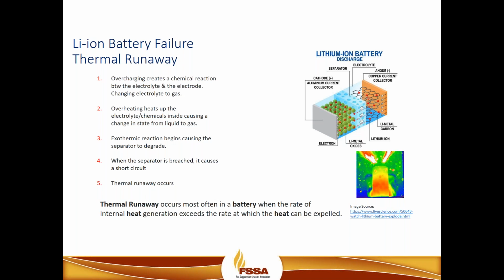If we look at what allows the electrolytes to become a gas, previously we talked about overcharging. So when overcharging is in the chemical process, the anode has too much current and it is touching the liquid. This allows for the chemical reaction to occur and change state from a liquid to a gas, and that's how it changes state. So as I mentioned, during this change of state, it happens at a relatively low temperature, usually at around, let's say, about 115 degrees Fahrenheit, which is pretty typical operating temperature for these type of batteries. There's not a lot of documentation on the market that shows that at that temperature, thermal runaway can be achieved. So there's good data out there that shows that the battery system can operate in those environments.